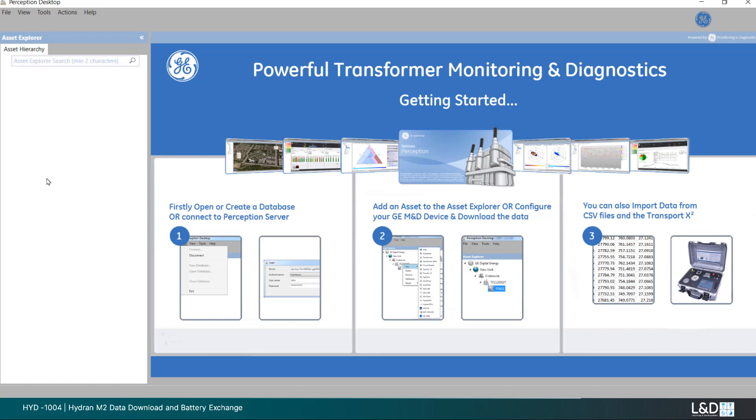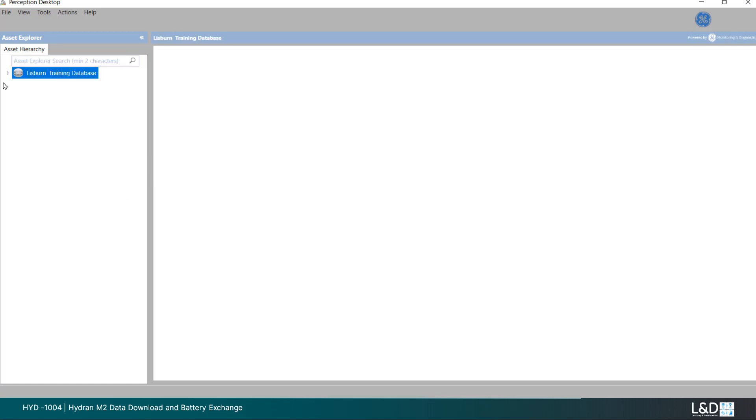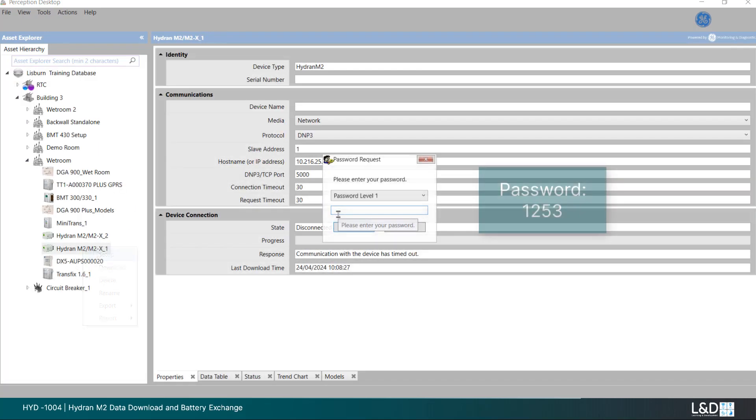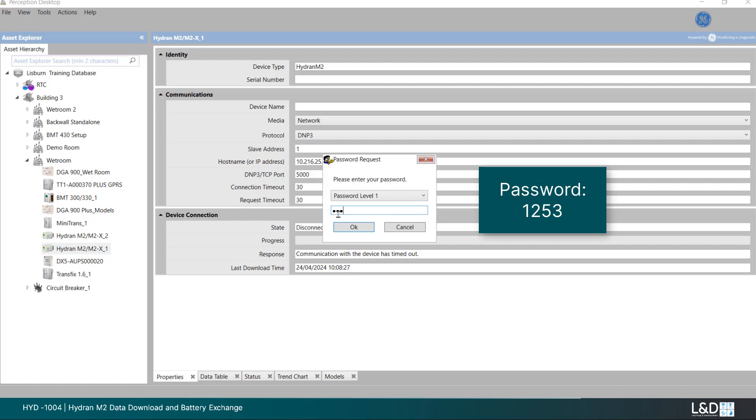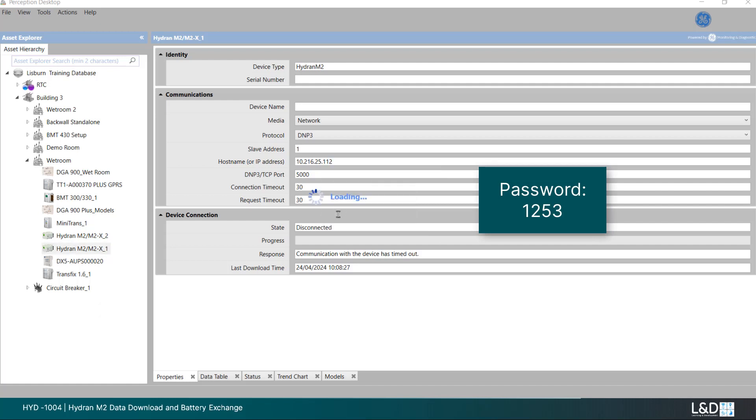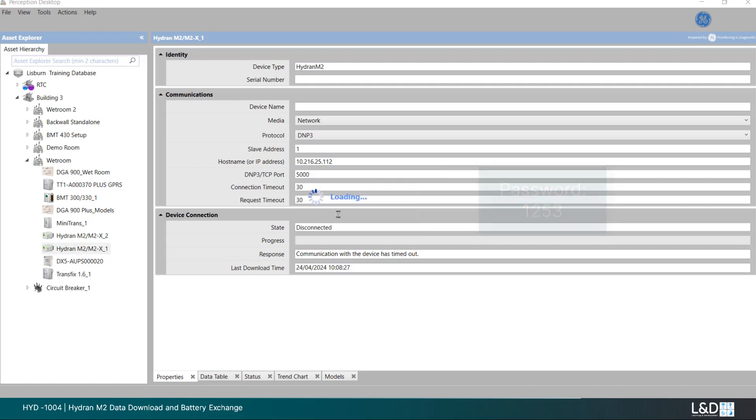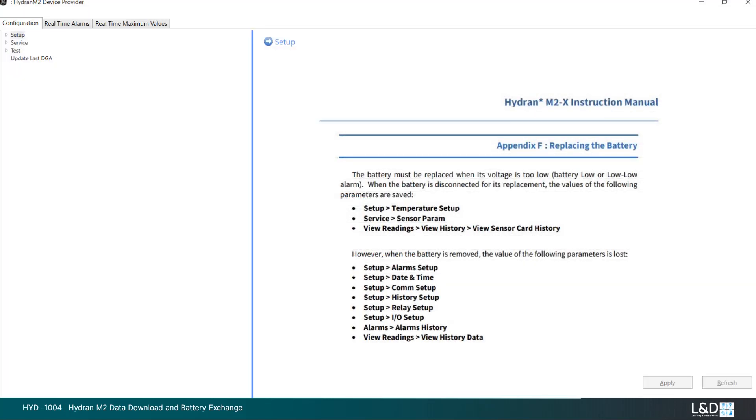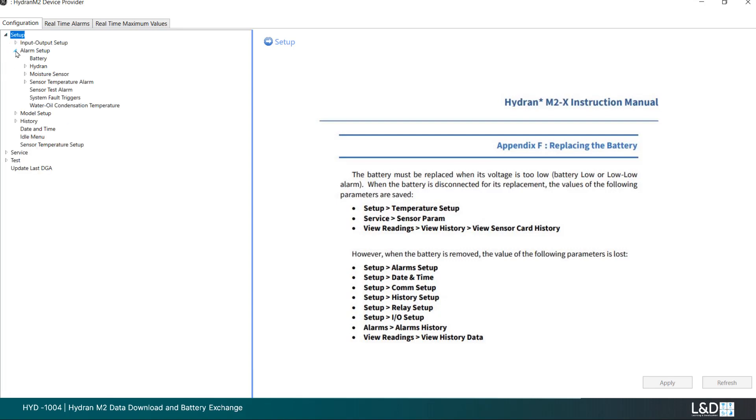Open the chosen software tool, if required with a temporary database, and set up your connection. Right-click on the desired device and choose setup. This will open a connection to the operating software that allows you to backup and save all the necessary data as per the support manual. This data may return to default settings and your setup should be re-entered after the monitor is re-energized. After data backup and download, power off the monitor and apply lockout tagout.